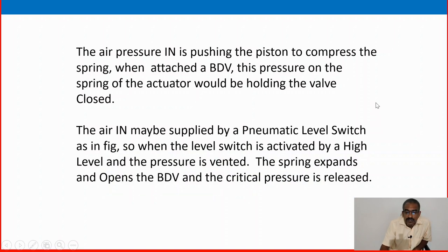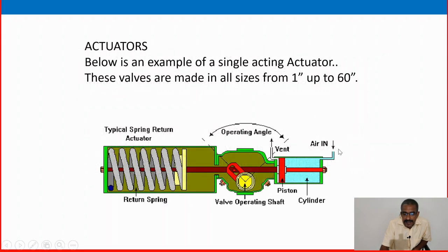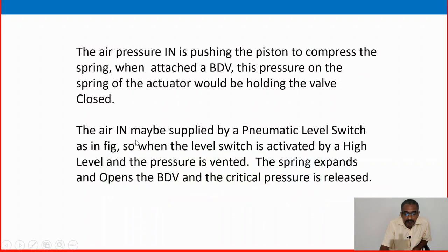The air pressure pushing the piston compresses the spring. When attached to a BDV, the pressure on the spring of the actuator would be holding the valve closed. Air in may be supplied by a pneumatic level switch, as in the figure. When the level switch is activated by a high level and the pressure is vented, the spring expands and opens the BDV as a critical pressure release.